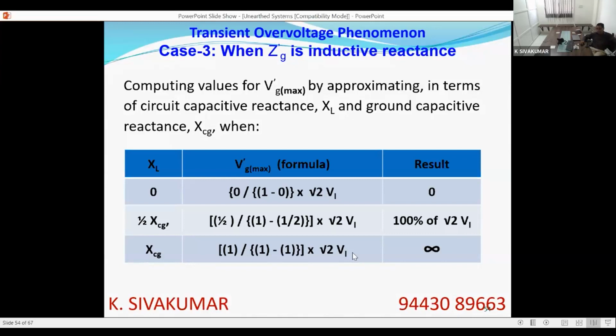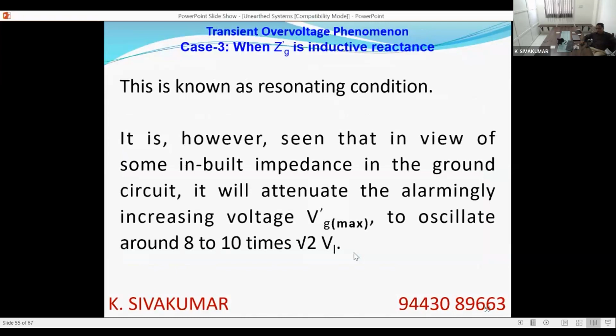Whenever the external impedance happens to equate the leakage capacitance of the system, there is a tendency of the voltage appearing across the external load going towards infinity. That is, very high voltage will be thrust upon the equipment and system during a single phase to ground fault in an unearthed system. So this is known as the resonance condition. It is however seen that in view of some inbuilt resistance in the ground circuit, it will be attenuated, not practically infinity. There have been calculations. It is seen that the voltage will float between 8 to 10 times the root 2 Vl.